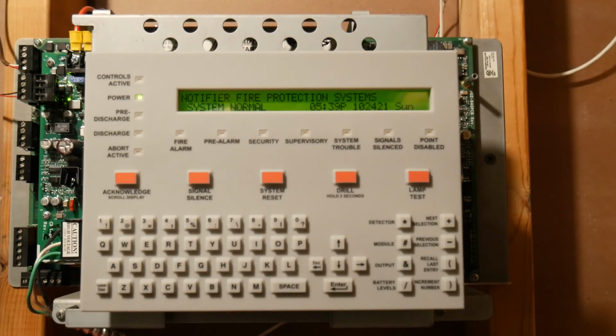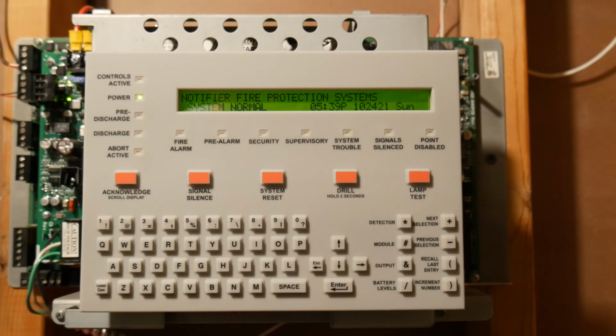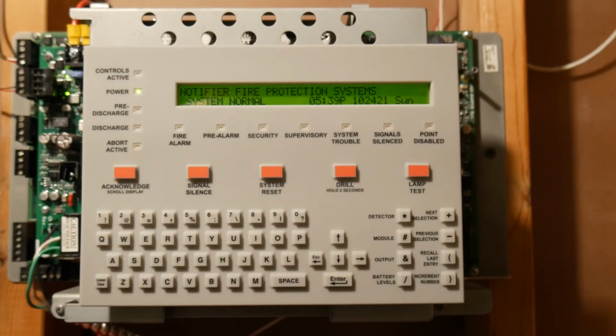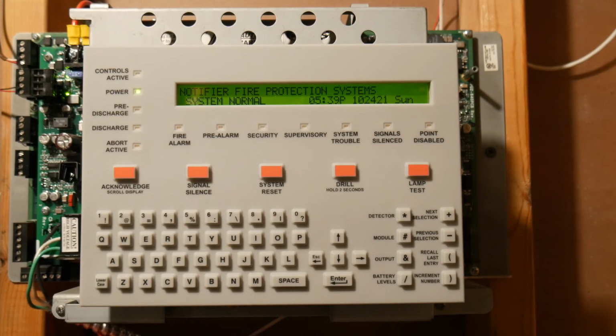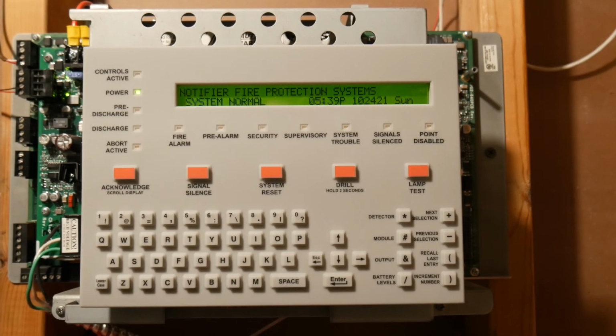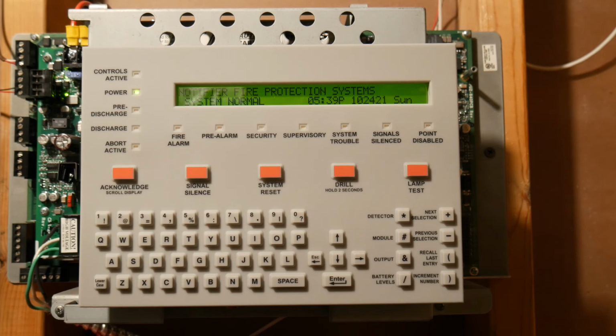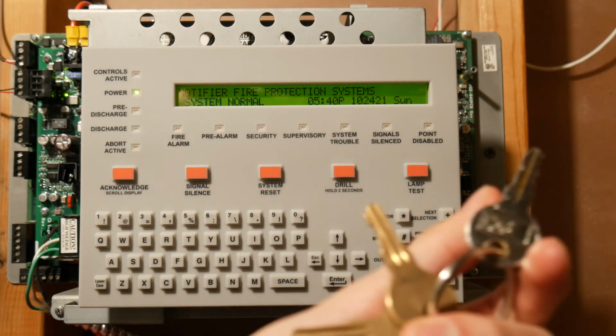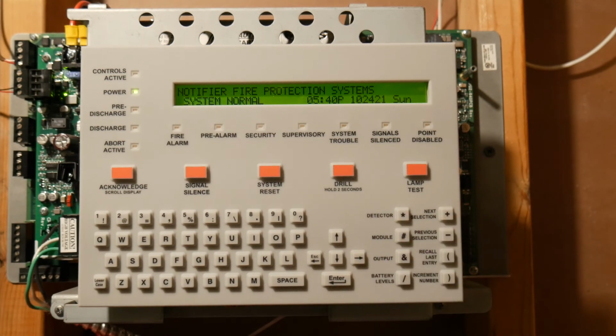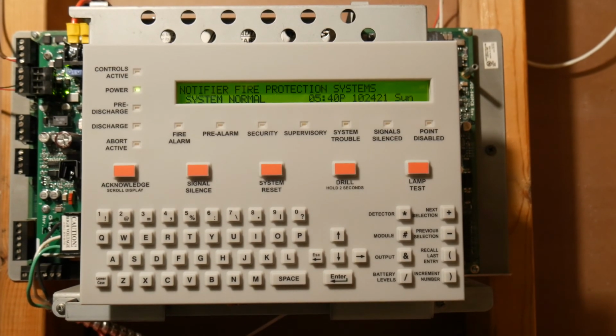So to make sure I successfully programmed it, I'm going to pull a device. I'm going to pull the agent release, which is right here, and we're going to see if it goes into alarm. And after we pull the agent release, we'll test a smoke detector and a pull station. So let me get my FCI key. I have my FCI key right here. And I'm going to pull the pull station. So I'm going to lift and pull.